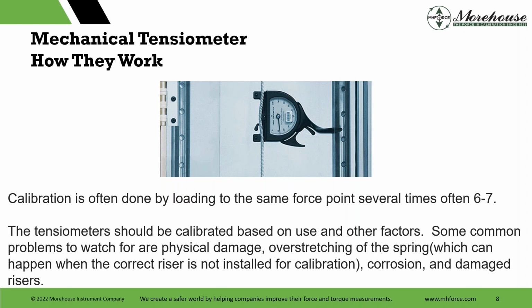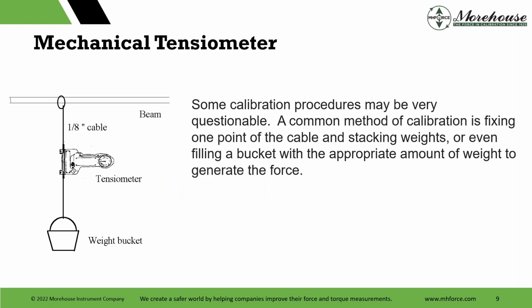Some common problems: easy visual inspection, physical damage, overstretching of the spring, which can happen when the correct riser is not installed for calibration, corrosion and damaged risers. So yeah, if somebody puts in the wrong riser, you can break it pretty easily. And sometimes people do not pay attention, so it's part of your procedure. Make sure the technician selects the right riser, assuming it has one. Some of the digital ones do not.